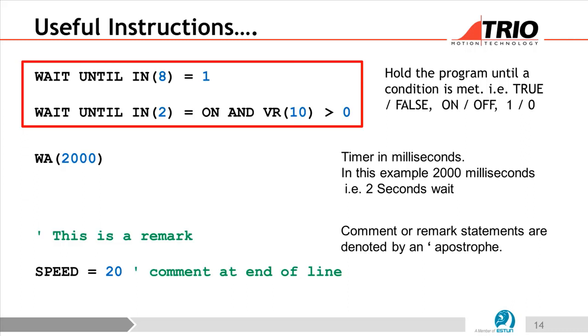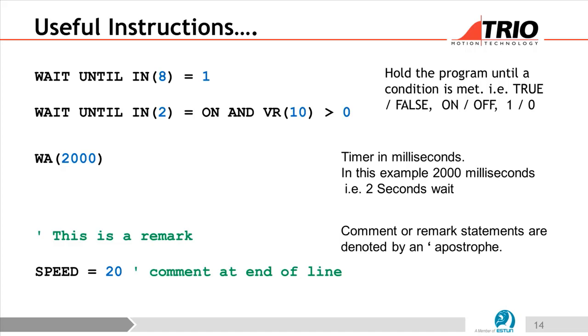We don't recommend using wait until, because sometimes if you don't know why the program is not working, when you have to diagnose, a wait until will just stay there unless the condition is met as true. So that's why we usually ask you to do a wait idle or wait loaded for move, but you can still use that if you know what the program is doing.